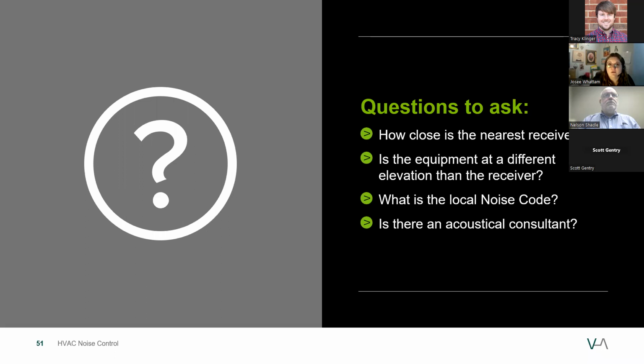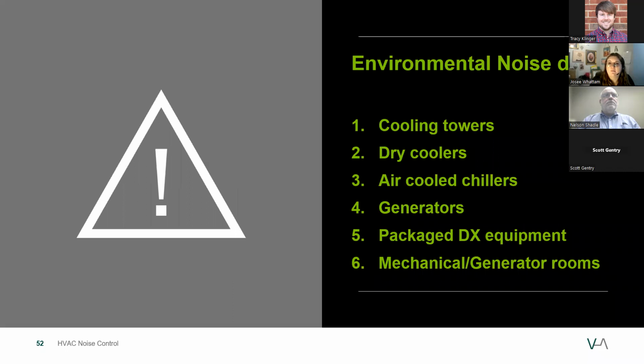To start looking for potential environmental noise issues, we need to ask ourselves a few questions. How close is the nearest receiver? Is the equipment at a different elevation than the receiver? What is the local noise code? And is there an acoustical consultant? The common environmental noise product culprits are cooling towers, dry coolers, air-cooled chillers, generators, packaged DX equipment, and mechanical or generator rooms.